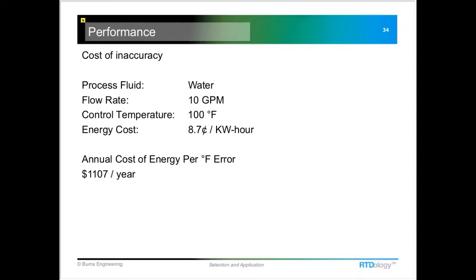An inaccurate measurement can be very costly. Our example shows $1,100 per year in losses — year after year — for a fairly mundane process: just 10 gallons per minute being heated about 40°F, like warming city water. It really pays to pay attention to how the sensor is installed, choose a good quality sensor, and get it as accurate as possible. If it costs a few hundred dollars more to do that, it's usually a good choice because it saves money in the long run.